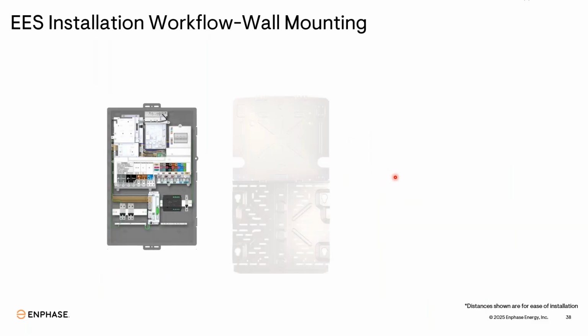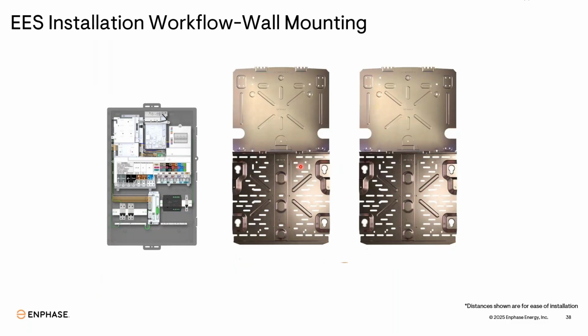This is the installation workflow. First you mount your controller, then your battery cover plate. Make sure the distance between both is 300 mm. 150 is the minimum distance, but we recommend keeping it 300 for ease of maintenance and ease of wiring, because you need to use screwdrivers, and for cable conduit entry you need some space there. So 300 mm will be sufficient for working there for ease of installation.